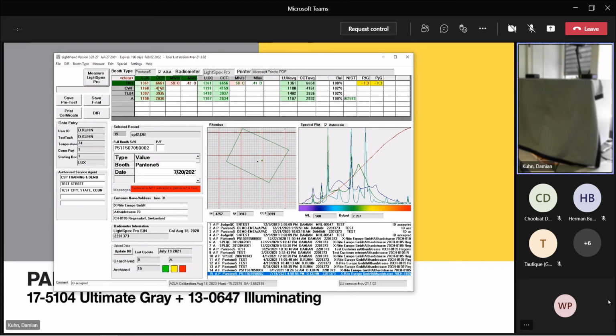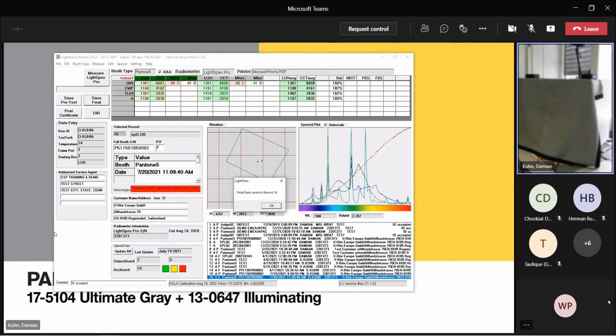Once you've taken all the readings on that light source, ensure the booth serial number is correct, ensure the customer address is correct, and then decide if this was your pre-test. You would probably now do some cleaning work and replacement of the bulbs, then store this as a pre-test. If you did that, or if the customer isn't concerned about it, you could directly save as a final test.